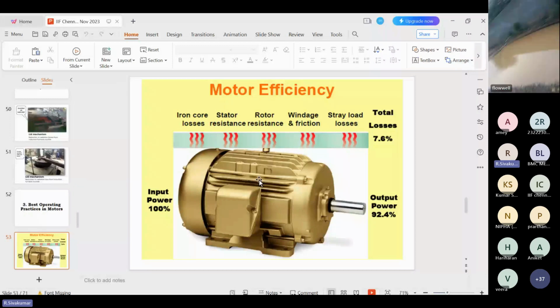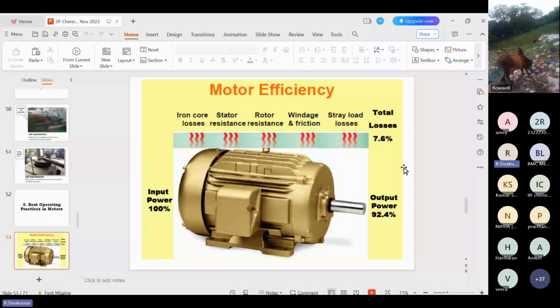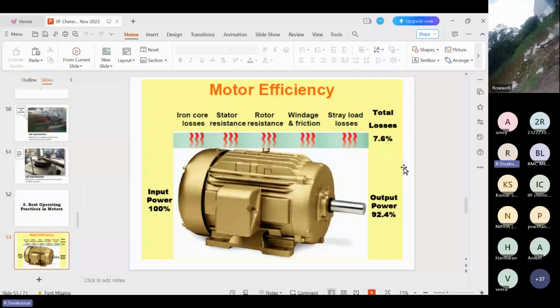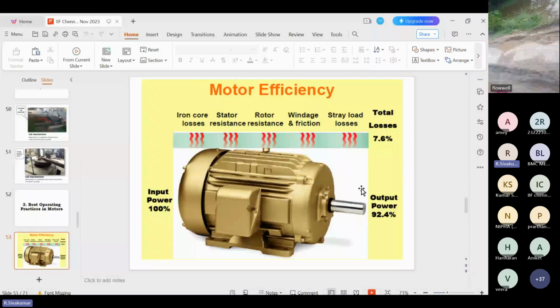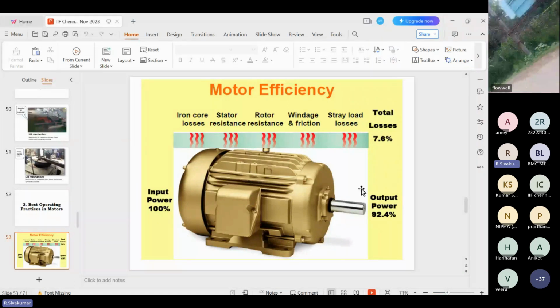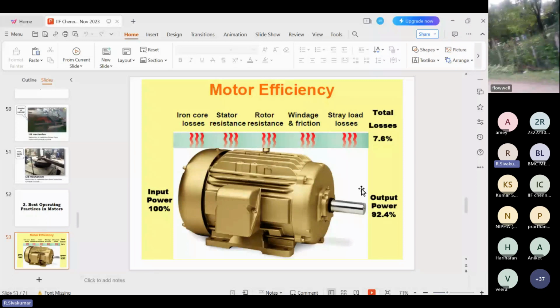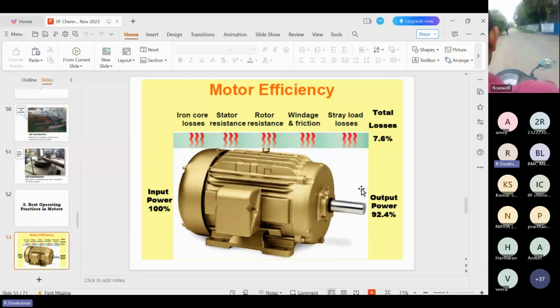Here the diagram shows this is the input power, this is the output power. In any motor, the nameplate says, for example, 10 HP motor, that is 7.5 kilowatt. What is the meaning of 7.5 kilowatt? The 7.5 kilowatt will be given at the shaft. That is the meaning of rated power. The nameplate does not say how much energy it takes; that depends on the efficiency level. For example, your motor is 90% efficient, 7.5 kilowatt, 10 HP. Then it gives 7.5 kilowatt at the shaft output. The energy input is 7.5 divided by 0.9, because 90% is your efficiency. So it comes to around 8.3 units drawn as input power.